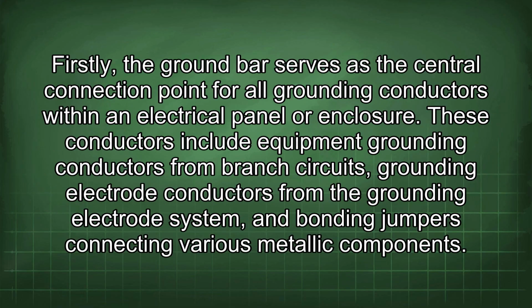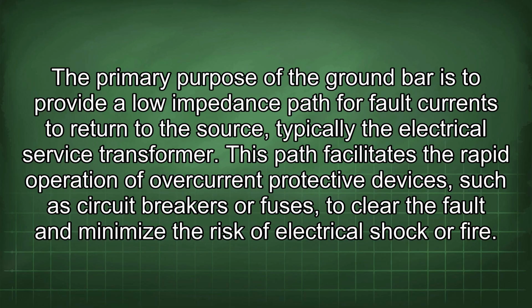Firstly, the ground bar serves as the central connection point for all grounding conductors within an electrical panel or enclosure. These conductors include equipment grounding conductors from branch circuits, grounding electrode conductors from the grounding electrode system, and bonding jumpers connecting various metallic components. The primary purpose of the ground bar is to provide a low impedance path for fault currents to return to the source, typically the electrical service transformer. This path facilitates the rapid operation of overcurrent protective devices, such as circuit breakers or fuses, to clear the fault and minimize the risk of electrical shock or fire.